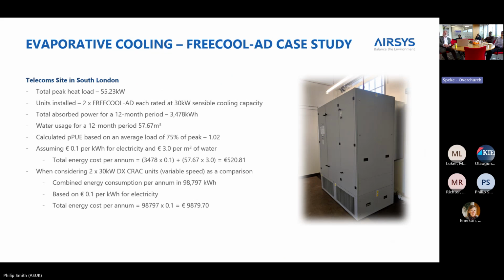Okay. We did a recent example of energy usage of these two units versus, and I can't read that. So with 55 kilowatts of load, 2 of the adiabatic units versus 2 DX CRACs, and the adiabatics were £500 odd to run for the year. The 2 CRACs were 10,000. Now, I do stress the point that the CRACs give you 24/7, 365 guarantee of conditions at all times, whereas the adiabatic has a small limitation 98% of the year. But in terms of an example of energy efficiency, there's such a huge dissipation between the two that when refrigerants are restricted, this sort of technology will become much more prevalent.